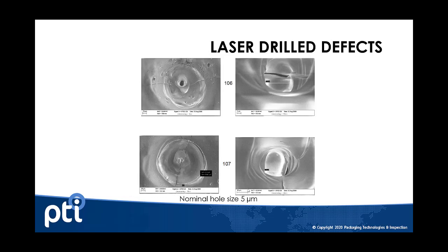One method for producing positive controls is laser drilling. In laser drilled defects, the laser is actually removing material from the defect site, and the defect size is validated after the fact using a certified flow measurement. That's how we can prove the defect is as close to a true defect as possible. You can see that these defects are not just pure holes, but are in fact complex in their geometry.